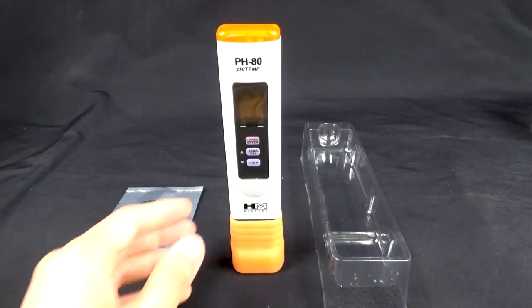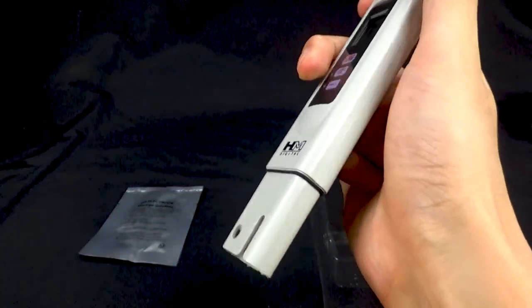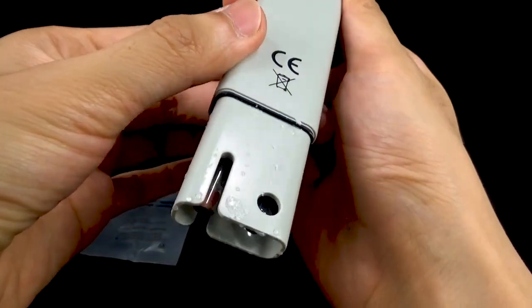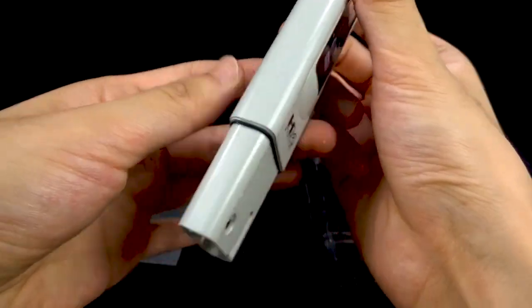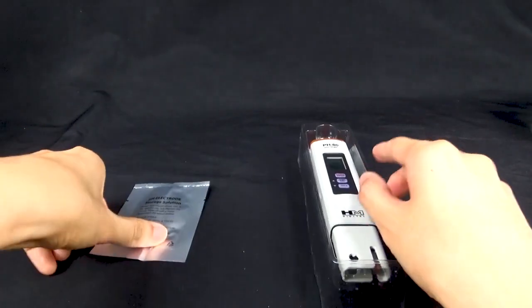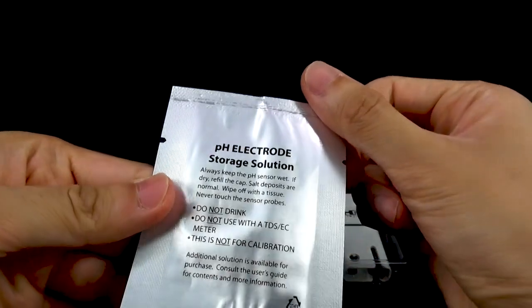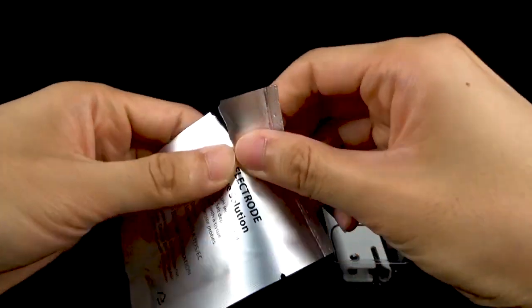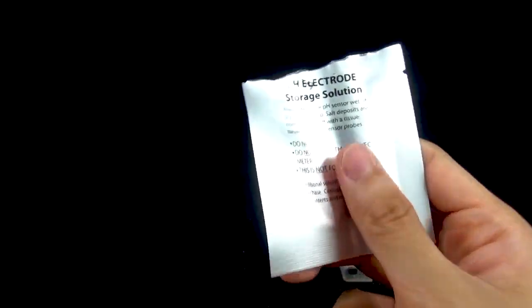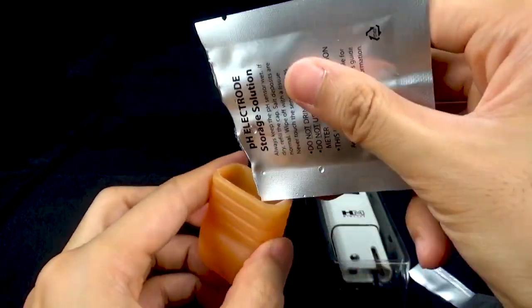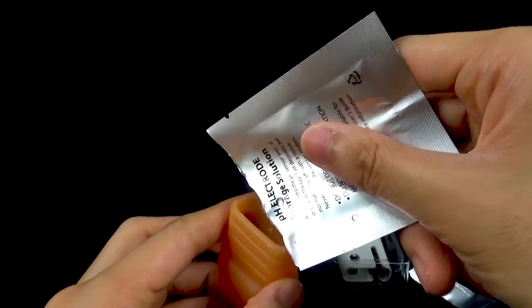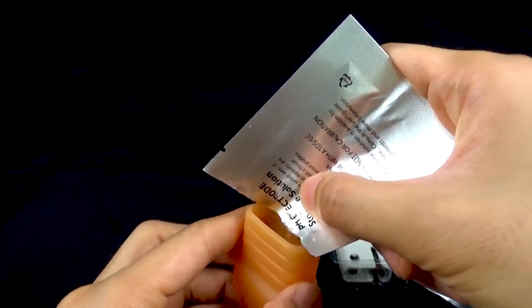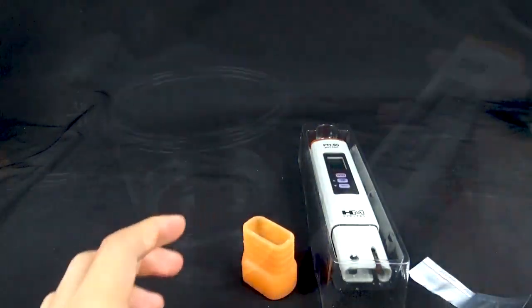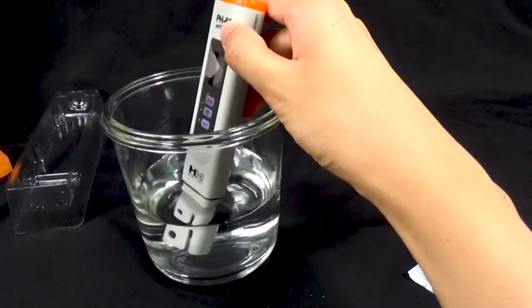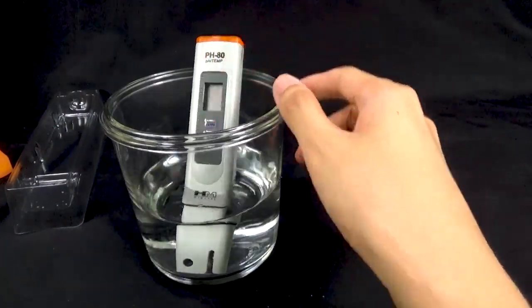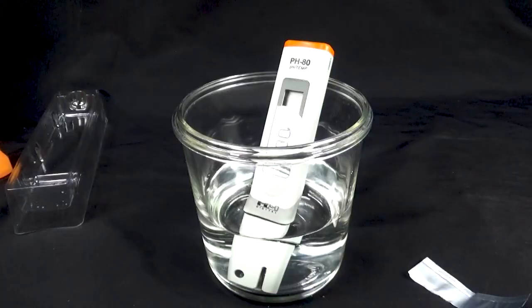Crystalline or salt residue may develop around the sensor during prolonged periods of meter inactivity. This is a common occurrence. It is just dried up potassium chloride storage solution that needs to be replenished. Open the 1 ml packet of storage solution and add the solution to the sponge in the silicone sensor cap, so the sponge becomes saturated in pH storage solution. Additionally, place the meter in tap water and leave it for 5 to 10 minutes to dissolve any residues on the sensor surface and reactivate the sensor. Recalibration after the procedure is highly recommended.